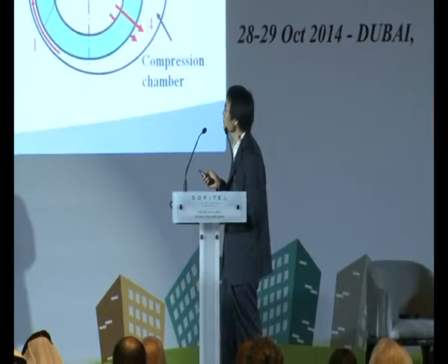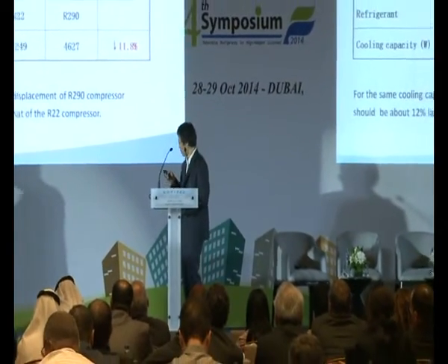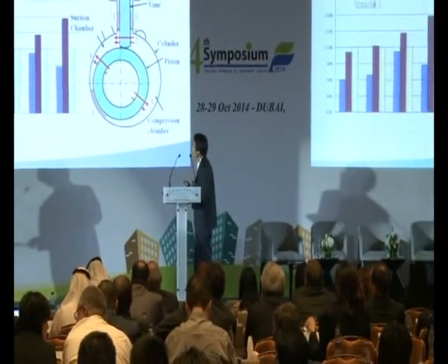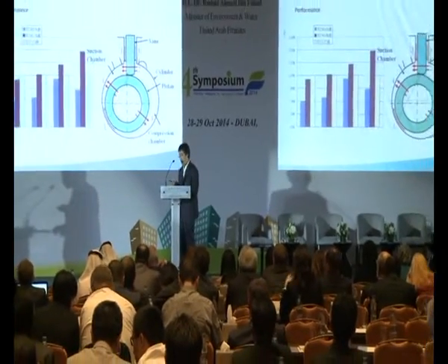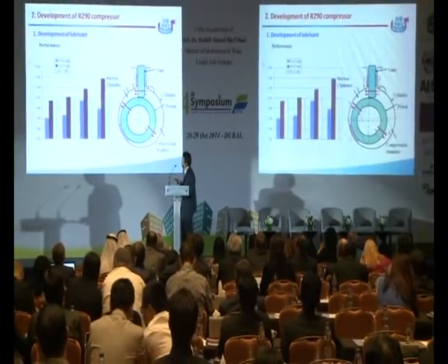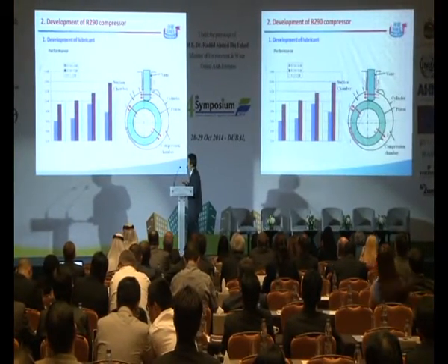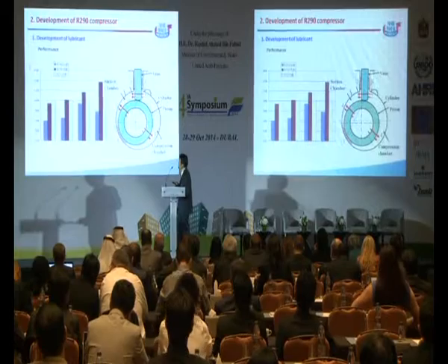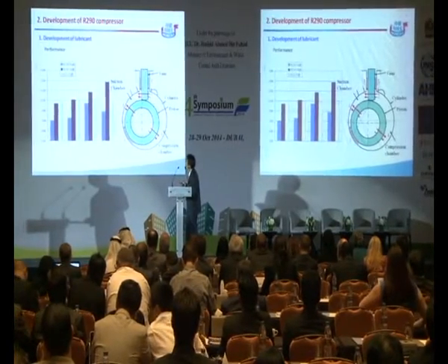Here we used 3 different oils to test the performance of the compressor. We can see the oil can greatly affect the performance of the compressor. So when we develop oil, we need to combine the above mentioned factors. It's a balance between these factors.